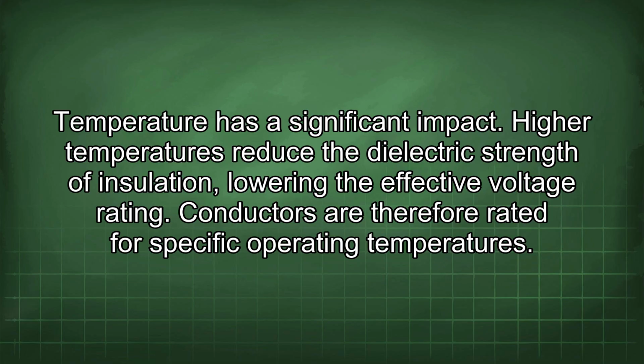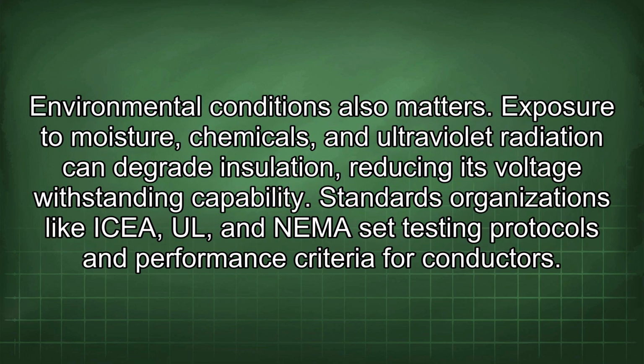Temperature has a significant impact. High temperatures reduce the dielectric strength of insulation, lowering the effective voltage rating. Conductors are therefore rated for specific operating temperatures. Environmental conditions also matter. Exposure to moisture, chemicals, and ultraviolet radiation can degrade insulation, reducing its voltage withstanding capability.